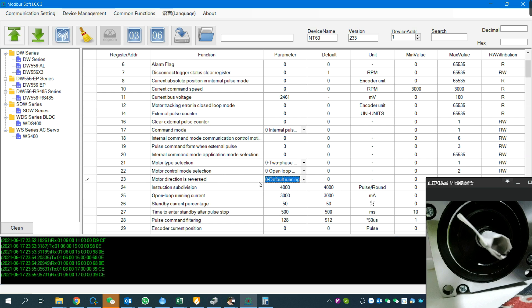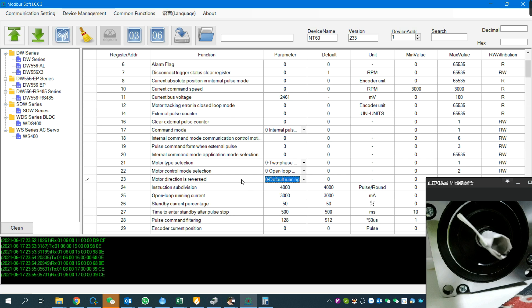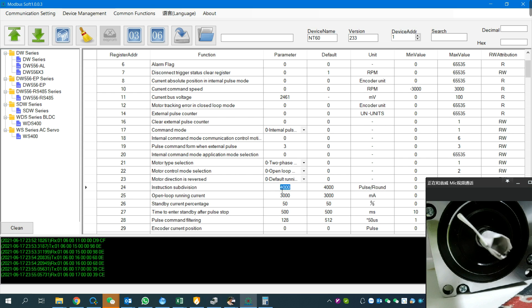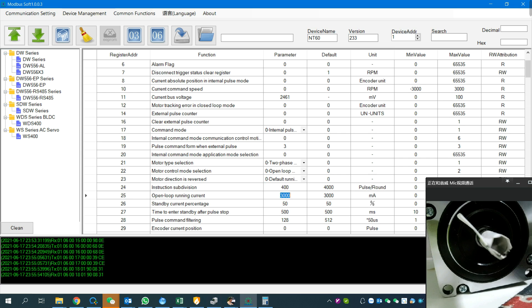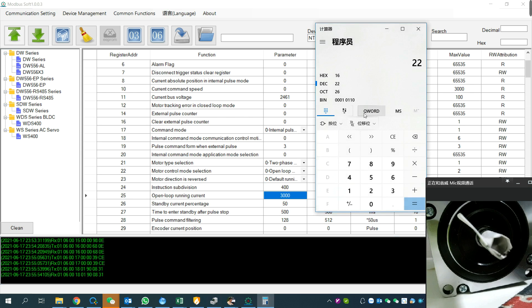Now we go to Step 2. We'll set the micro step and the current for the driver. Micro step is register 24 - subdivisions or micro step setting. The default setting is 4000. Now I want to change it to 400. The micro step setting will change to 400, which means the motor needs 400 pulses to run for one revolution. Just hit enter. We're writing to this register the value 0190. Check - 0190 is 400 in decimal.